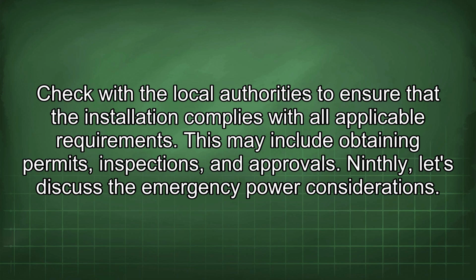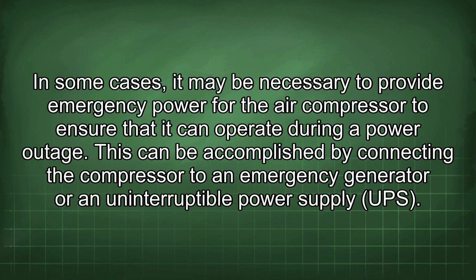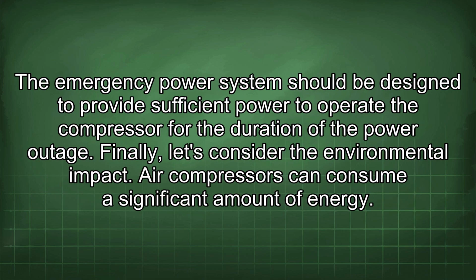Ninthly, let's discuss the emergency power considerations. In some cases, it may be necessary to provide emergency power for the air compressor to ensure that it can operate during a power outage. This can be accomplished by connecting the compressor to an emergency generator or an uninterruptible power supply, UPS. The emergency power system should be designed to provide sufficient power to operate the compressor for the duration of the power outage. Finally, let's consider the environmental impact.